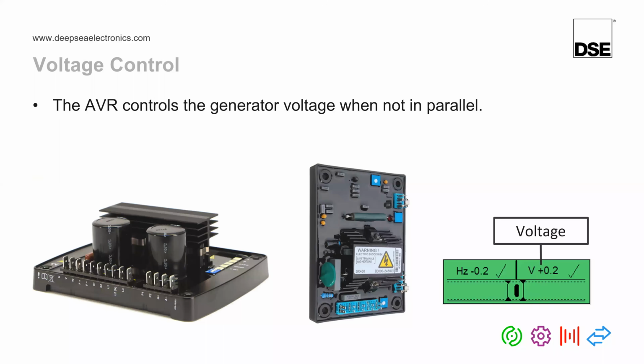The next part of synchronizing is controlling the voltage. The voltage is controlled by something called the AVR, automatic voltage regulator, inside the alternator. Again, there are many different AVRs out there. There are some examples on the slides for you to see, but effectively it's controlling the voltage of the generator, which is shown on the synchroscope here. The way the AVR works, it changes the excitation current to the alternator, which in turn changes the voltage.